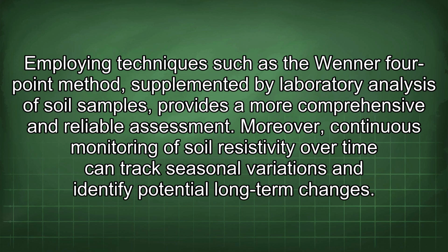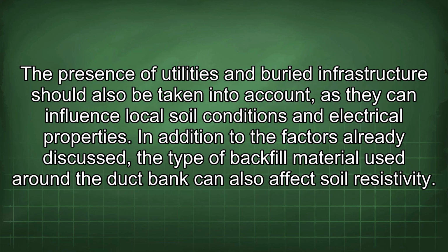Employing techniques such as the Wenner four-point method, supplemented by laboratory analysis of soil samples, provides a more comprehensive and reliable assessment. Moreover, continuous monitoring of soil resistivity over time can track seasonal variations and identify potential long-term changes. The presence of utilities and buried infrastructure should also be taken into account, as they can influence local soil conditions and electrical properties.